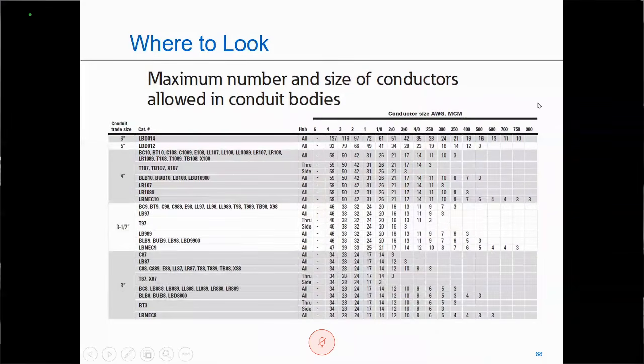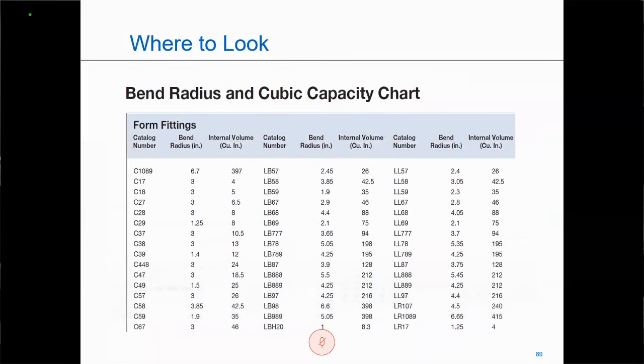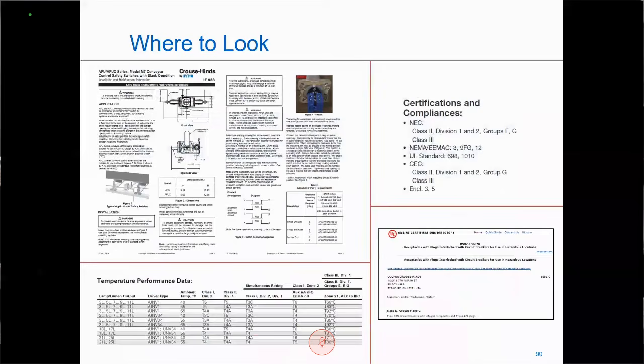Manufacturers have technical documents. So if you're concerned about how many conductors of what particular size can fit into a trade size of a conduit body, they'll have documents that will guide you in that direction. Also, manufacturers will have bending radius and cubic inch capacity charts that will guide you. Also, instruction sheets. They're going to give you detailed instructions of how to comply with the code.